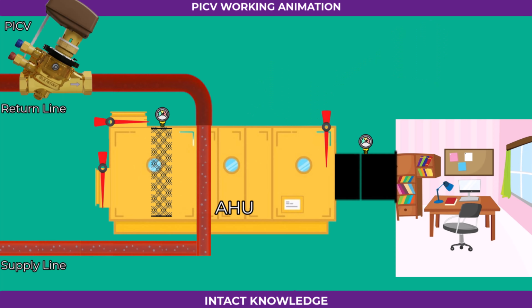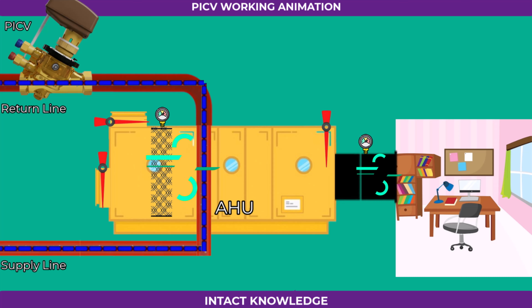The PICV is always installed on the return line of the AHU. This is a common question in interviews. Where is the PICV located in an AHU system? The answer is, it's always on the return side, never on the supply. Chilled water enters the cooling coil of the AHU through the inlet and exits through the outlet. As the chilled water circulates, the coil surface gets cold. When warm air passes across the coil, it loses heat and cools down, creating comfortable air for the room.